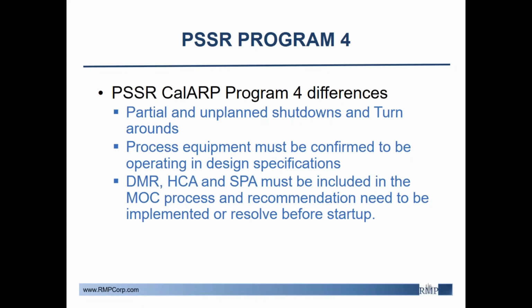So it kind of ties in with construction checks, but now they're specifically calling out you need to make sure that if you're going to start up and you've made changes or shutdowns have occurred, that when you start up, you're operating within your safe design limits and not running, let's say, just pressure above MAWP or running flow rates beyond what your system can handle.